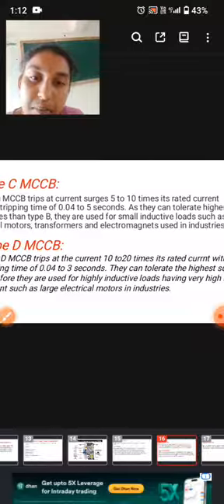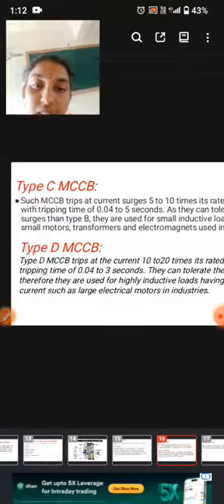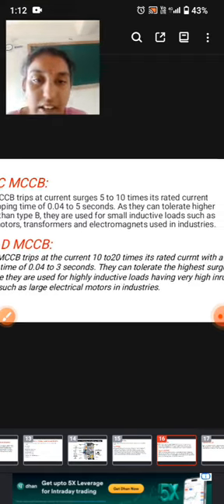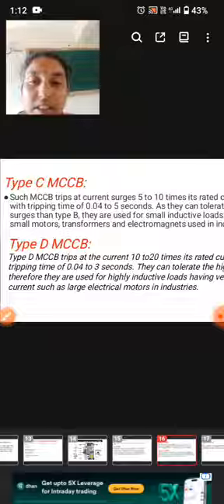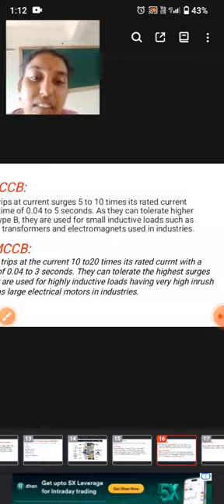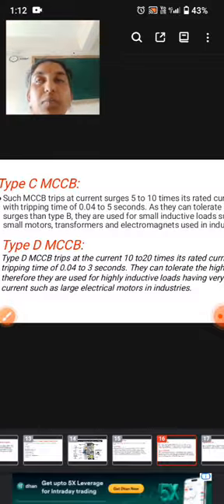Type D MCCB. Type D MCCBs trip at currents 10 to 20 times their rated current, with a tripping time of 0.04 to 3 seconds. They can tolerate higher surges, therefore they are used for highly inductive loads having very high inrush current, such as large electrical motors in industries.